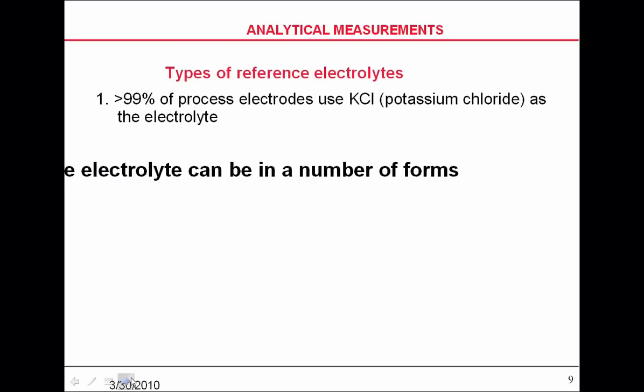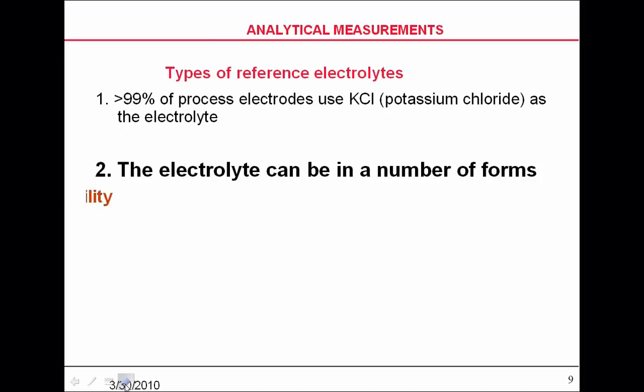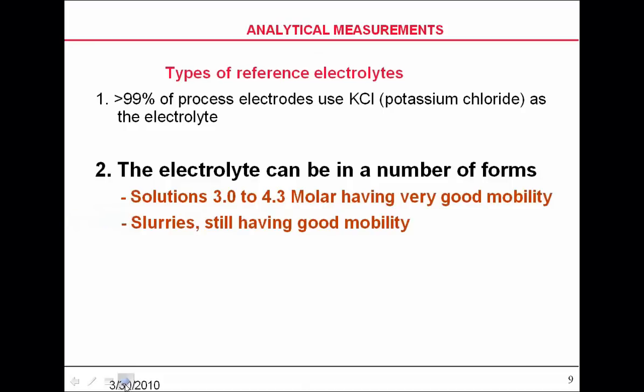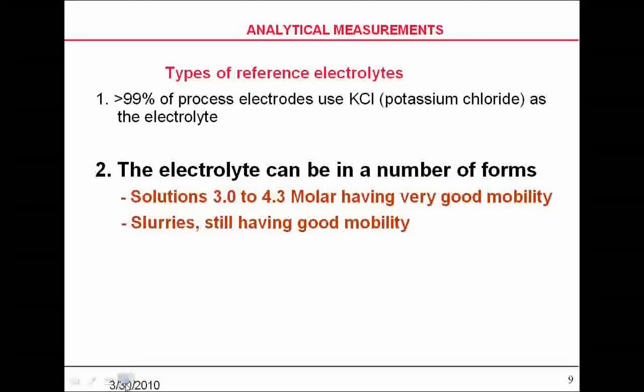About 90% of the measuring electrodes that are in the field today use potassium chloride as the reference electrode electrolyte. But there are other agents that can be used. You can use potassium chloride that's in the 3 to 4.3 mole area because it gives you good mobility.